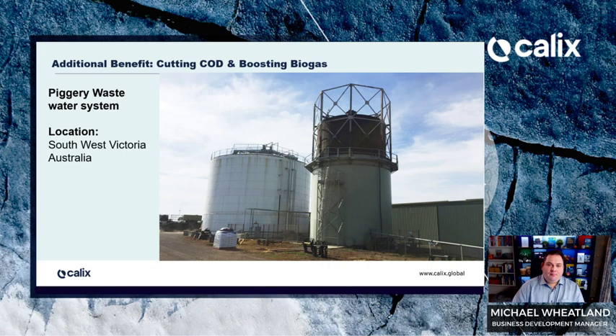It does that by two mechanisms. Number one is around the bulk pH and alkalinity control. Being a magnesium hydroxide, it is naturally alkali, so it will improve and stabilize the bulk pH. But also, due to its high surface area, it's able to boost the bacteria that produce the methane within the anaerobic system. That's going to result in more biogas coming off any system that you've got a collection system on, which assists in boosting energy output.